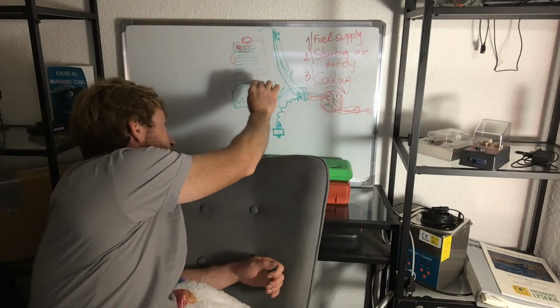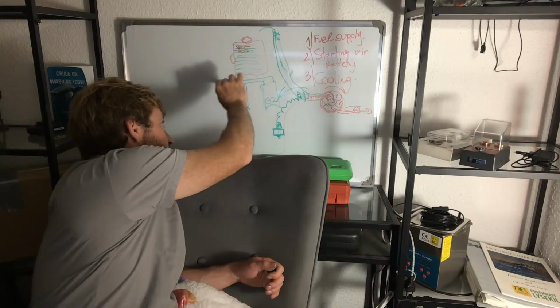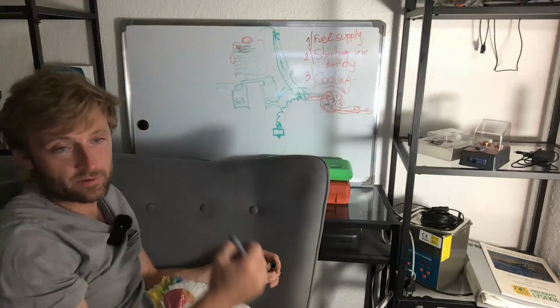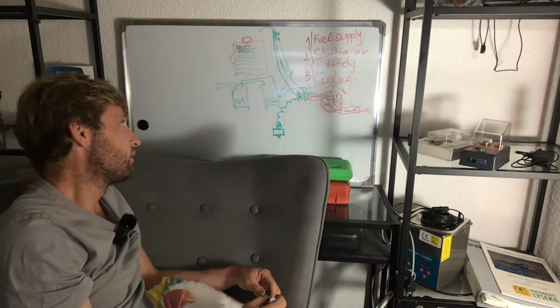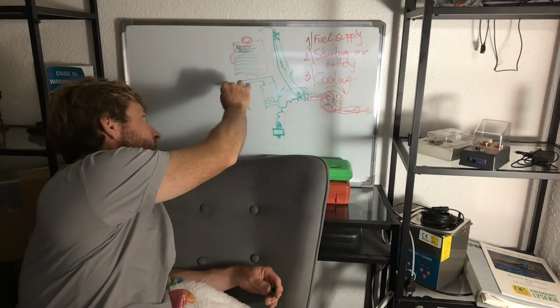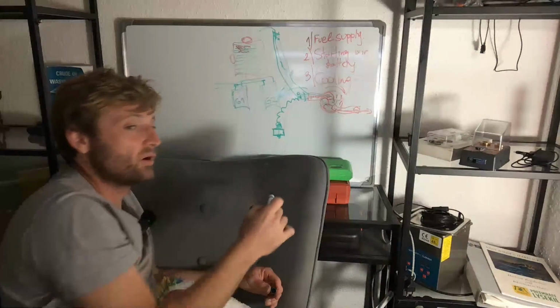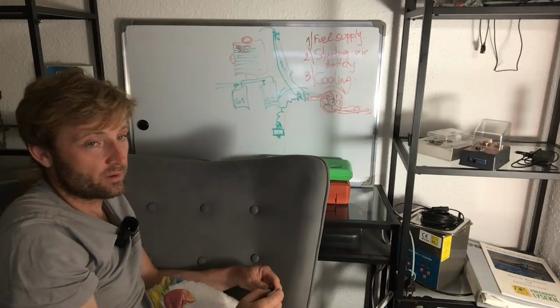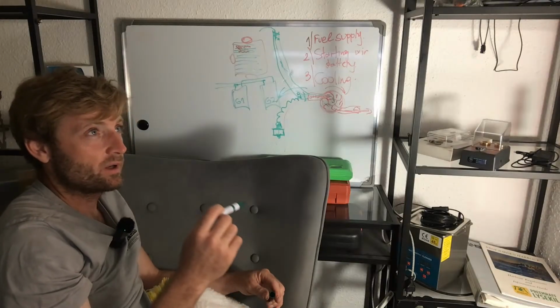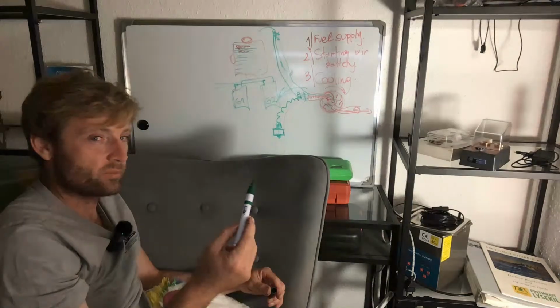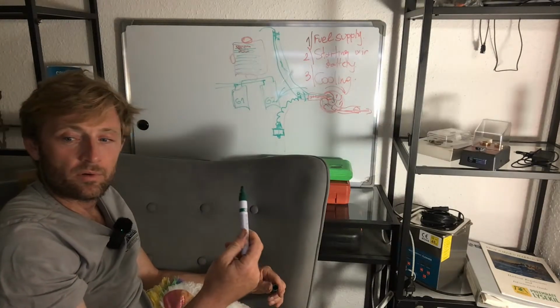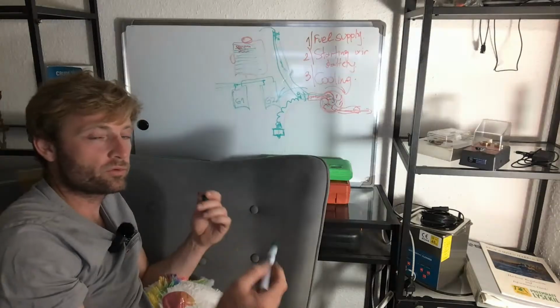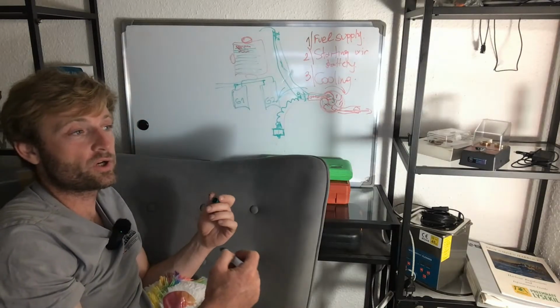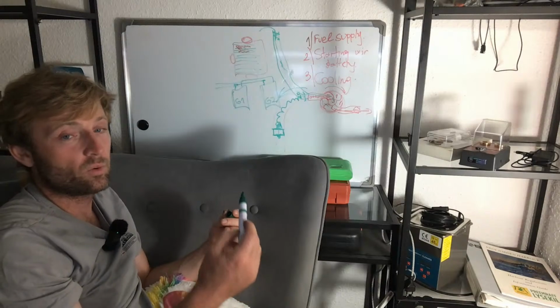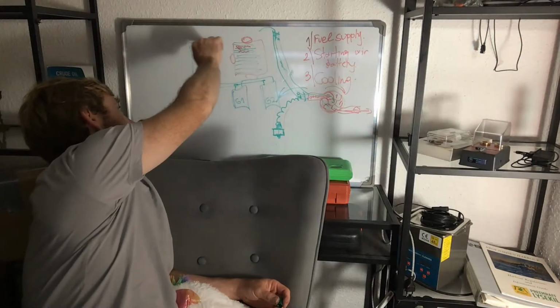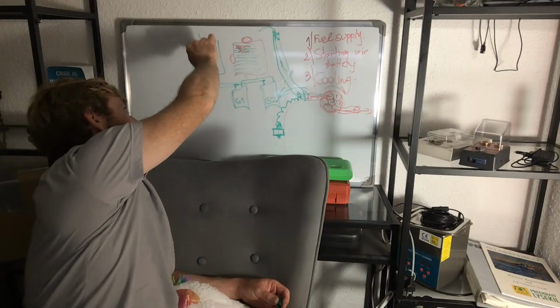Most probably they have the same cooling supplied from the freshwater system, if that is the case. There are also some three-way valves here that are temperature adjusted. Probably it can be from here, because these temperature adjustments are regulated by the pressure, if I'm not wrong, of the pump. So if your pressure is low, you have to check your pressure. You have to check how this valve is opening — is it opened, or does it follow the temperature increase of the engine and start to operate?